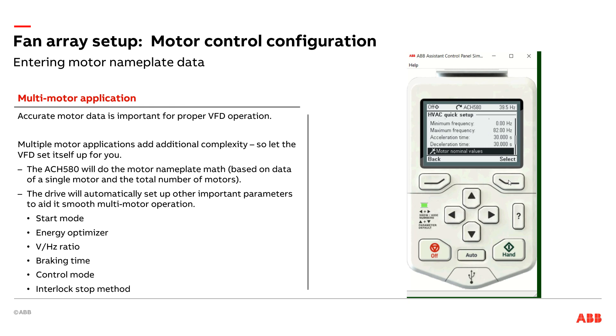And there you go. You just set up an ACH580 VFD to run a multiple motor application. You told it how many motors you had and what the motor nameplate data was for a single motor — and we're assuming all the motors are identical, which is an important key part of this functionality. All those key parameters and settings that are a good idea to change for a multiple motor application were automatically changed, and we gave you a summary of what was changed so you can go back and override anything if needed. So there you go — multiple motor setup with the ACH580. If you have any questions, reach out to your local ABB representative or your friendly ABB factory application engineer. Thank you.